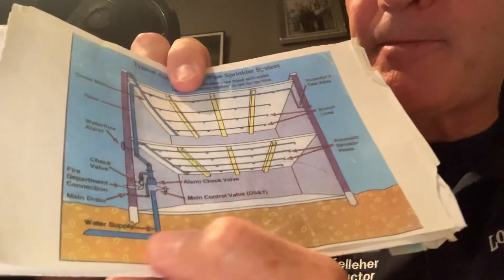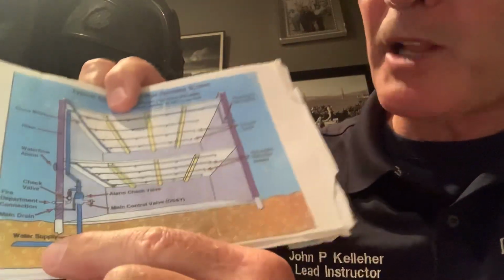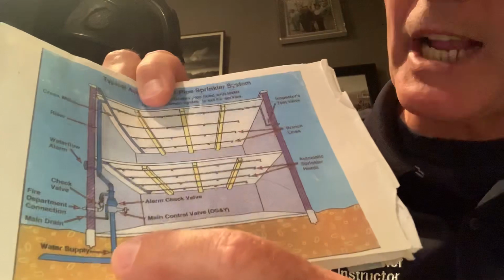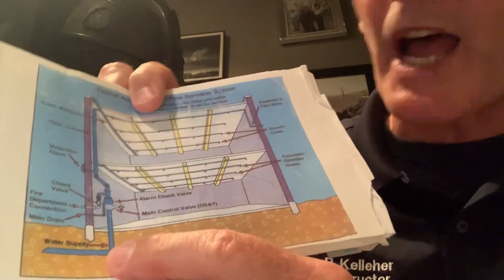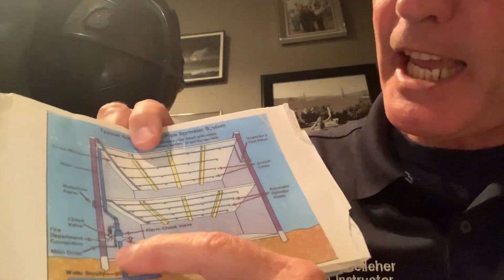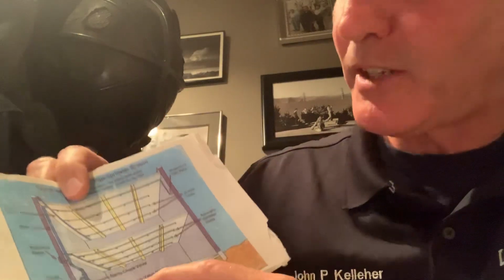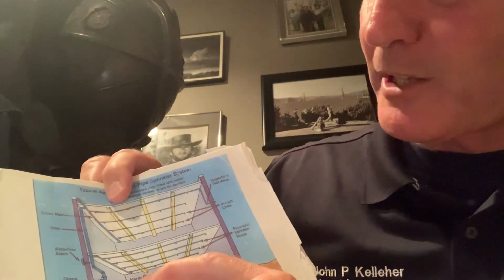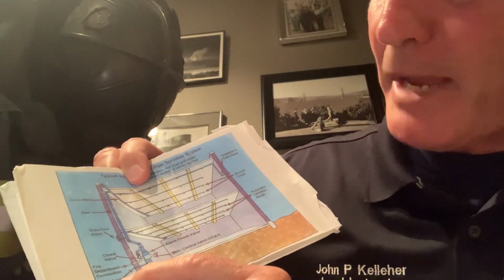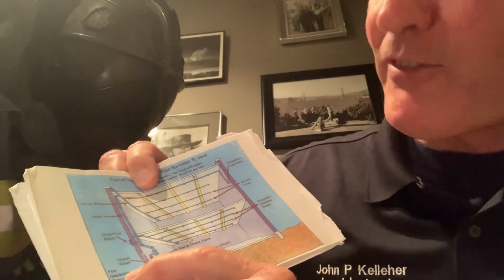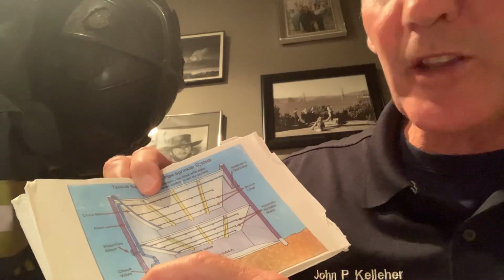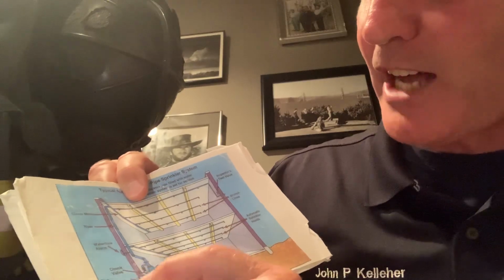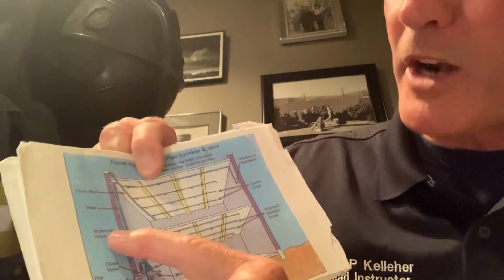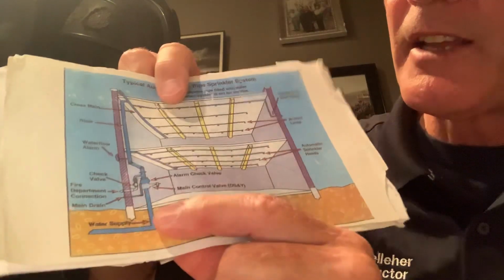On the bottom here is where the water supply is. Then there's one pipe going up, which they call the riser. Need to know that. Off the riser are all these different parts: the main control valve, the alarm check valve, the main drain, the fire department connection, the FDC we call it in the fire service, the check valves, and the water flow alarm up here, and that's all on the riser.